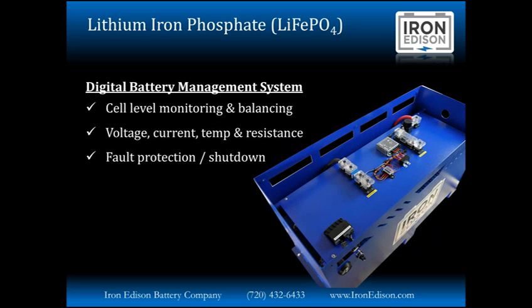All of our lithium iron batteries include a digital battery management system, which is pretty much necessary with any lithium battery. Our BMS does cell level monitoring and active balancing of each cell in the battery pack. We're looking at the voltage, the current, the temperature, as well as the resistance of each individual cell. And we have the ability to actively balance and correct any minor deviations with each individual cell. Should a cell get out of tolerance to the level that we cannot actively correct it, there's fault protection and a shutdown mechanism built into the battery, so the battery will shut down if it can't compensate for anything that's out of parameters.